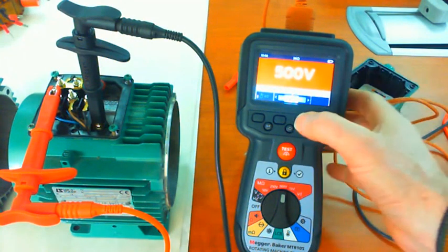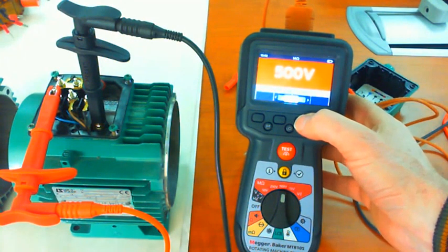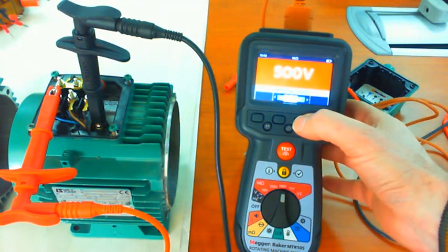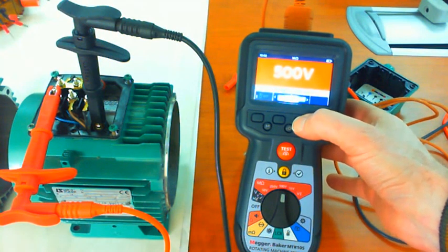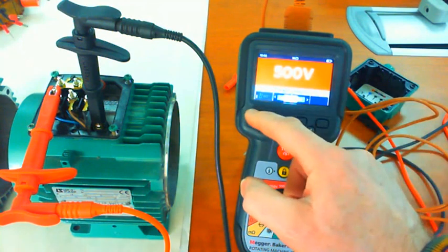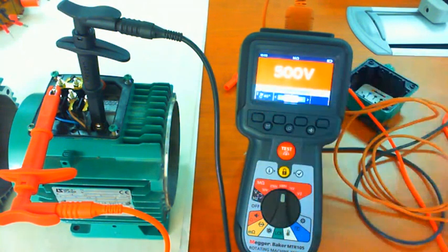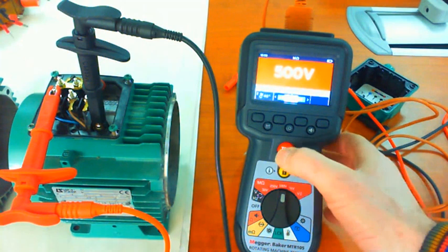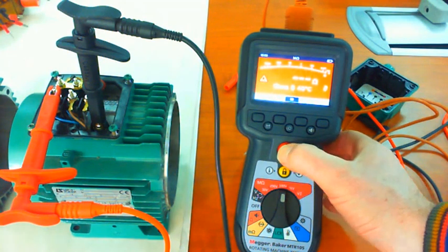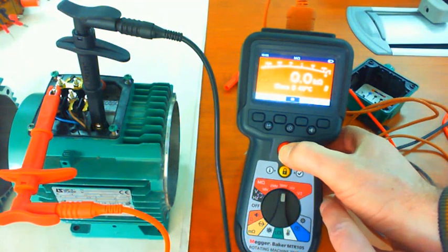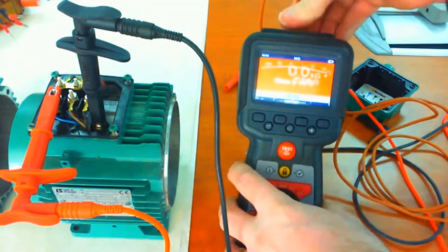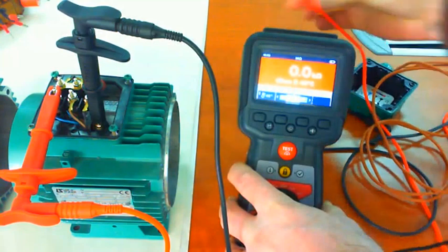And it's telling me here I've got IR. I've also got the 3-phase option, PI, time test, DAR or dielectric absorption, back to IR. And I can now switch on my temperature correction mode. So now if I run a test, I need to connect my leads again, otherwise I have no reading.